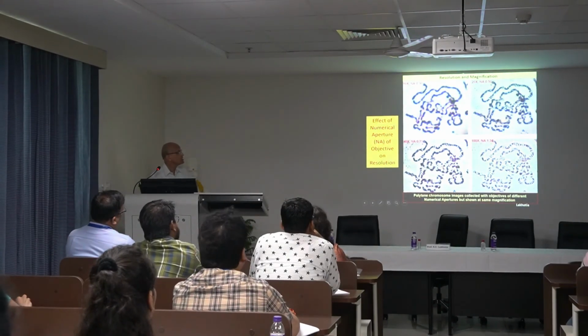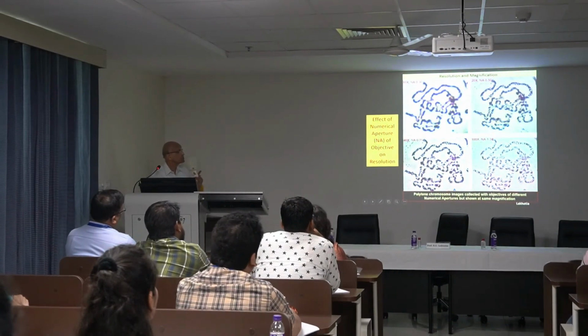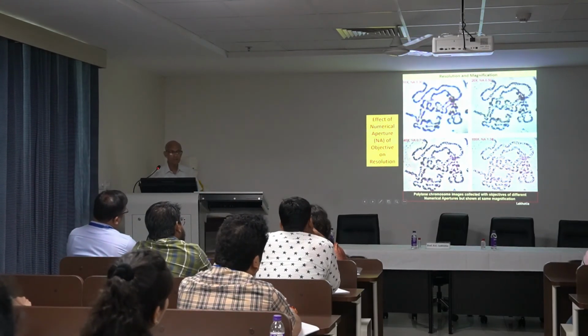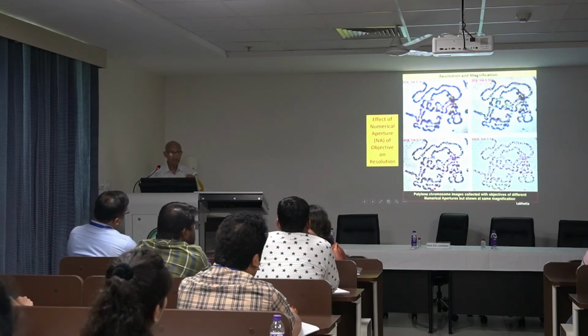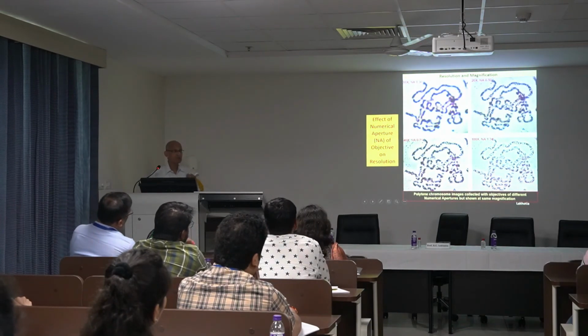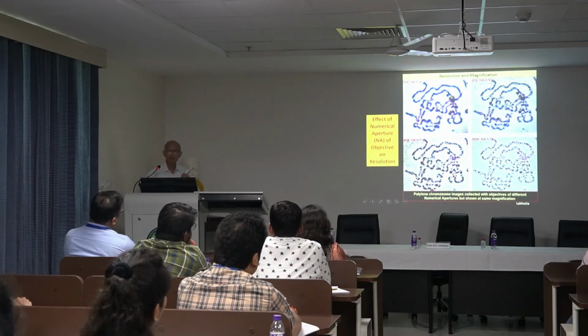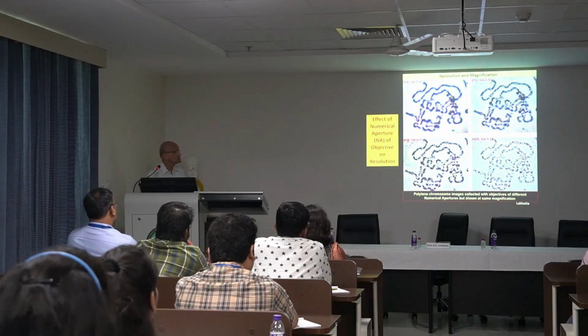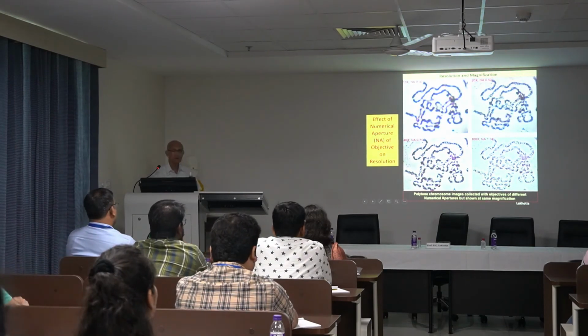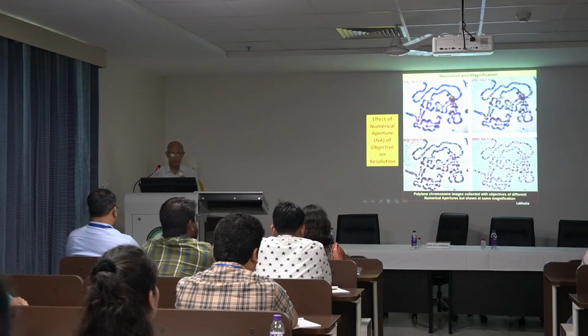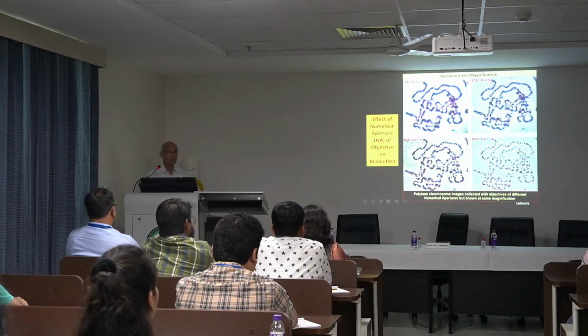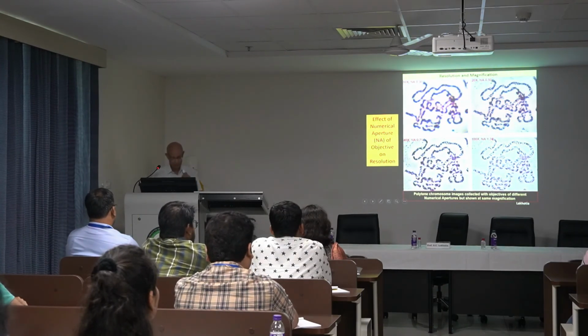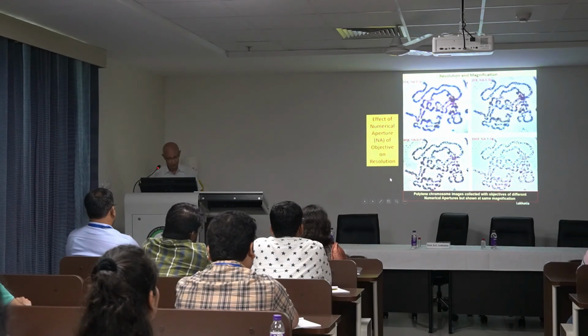image, it doesn't resolve. For example, the 10x objective image that you saw is magnified to the same level as this 100x objective, and you can see the difference. We are simply magnifying, we are not able to resolve. So the quality of the image depends on the original resolution at which it is taken, not just on magnification, be it digital or otherwise. That doesn't serve the purpose, and that's where the quality of the objective and the quality of illumination that is set up provide you the real quality images, and that must be regularly followed.